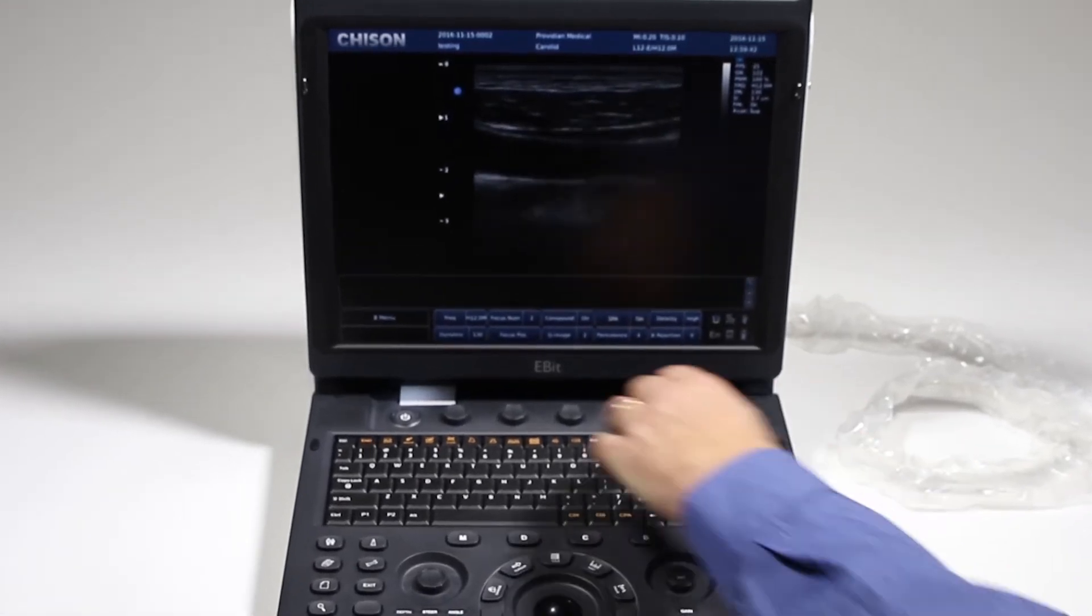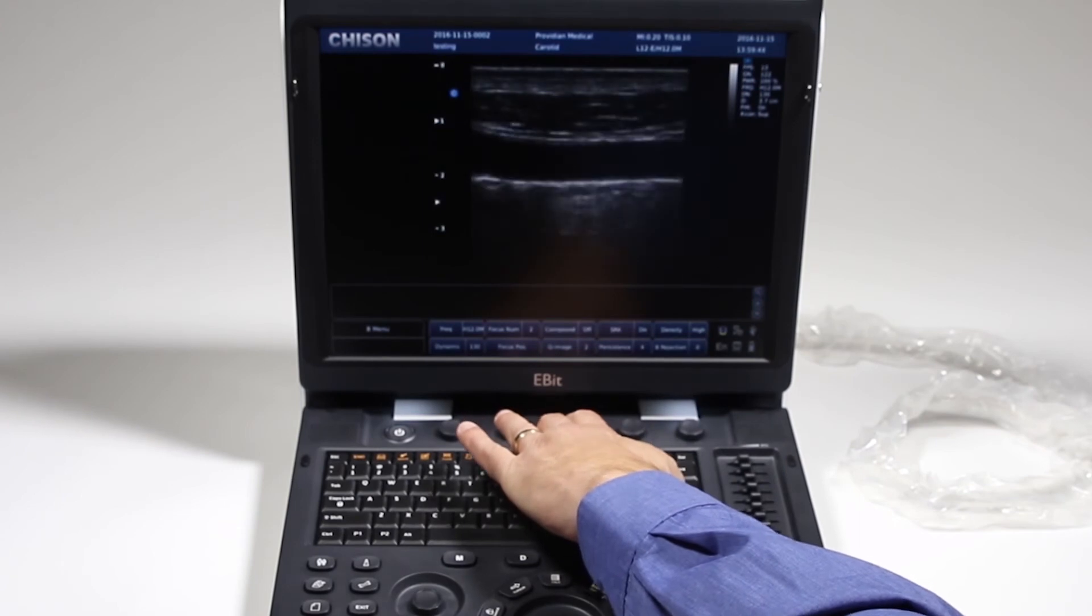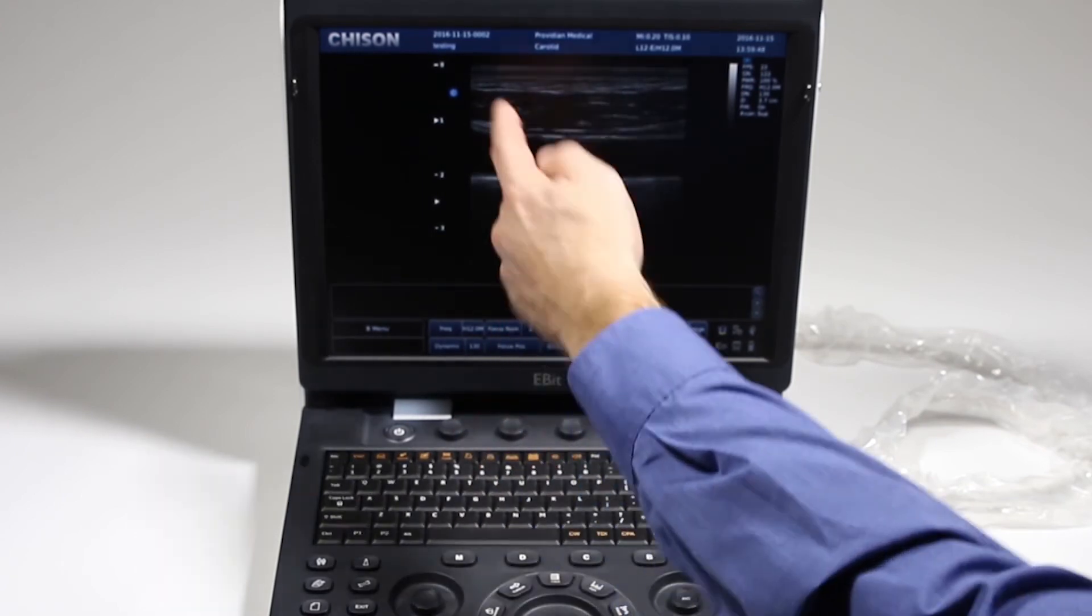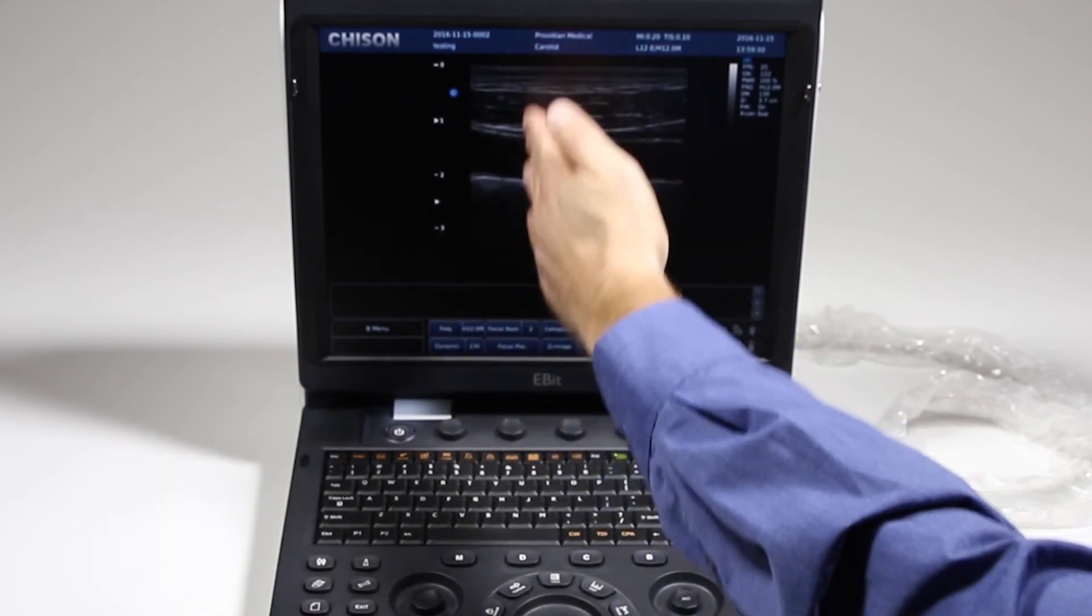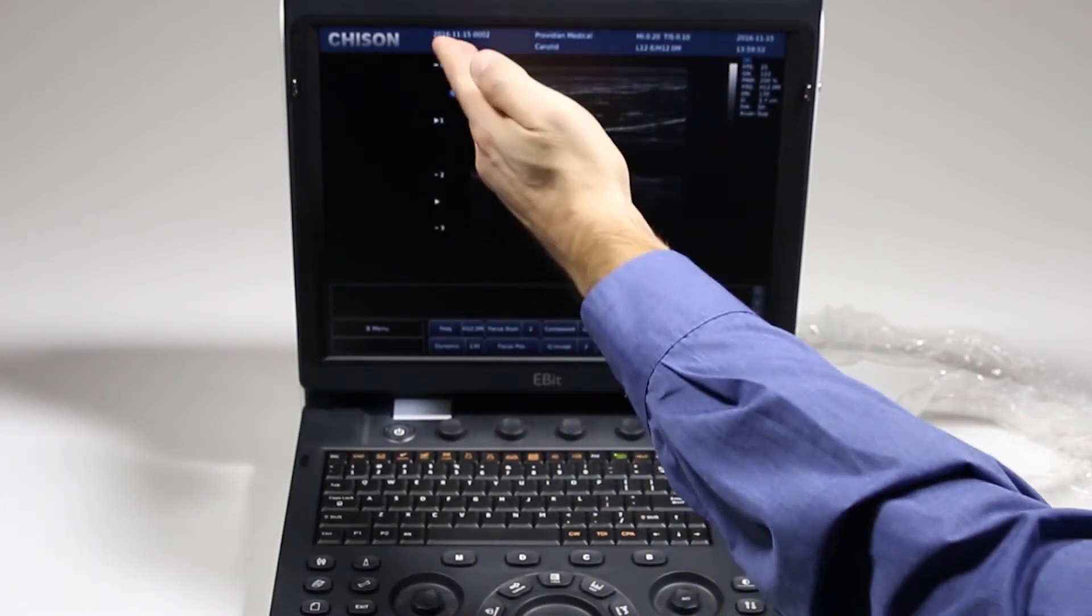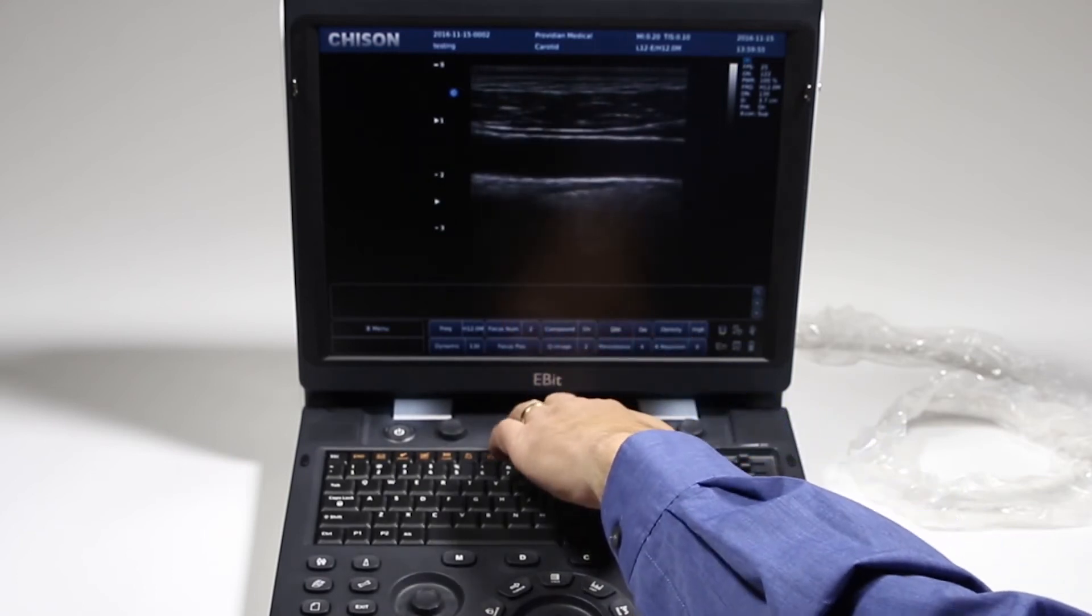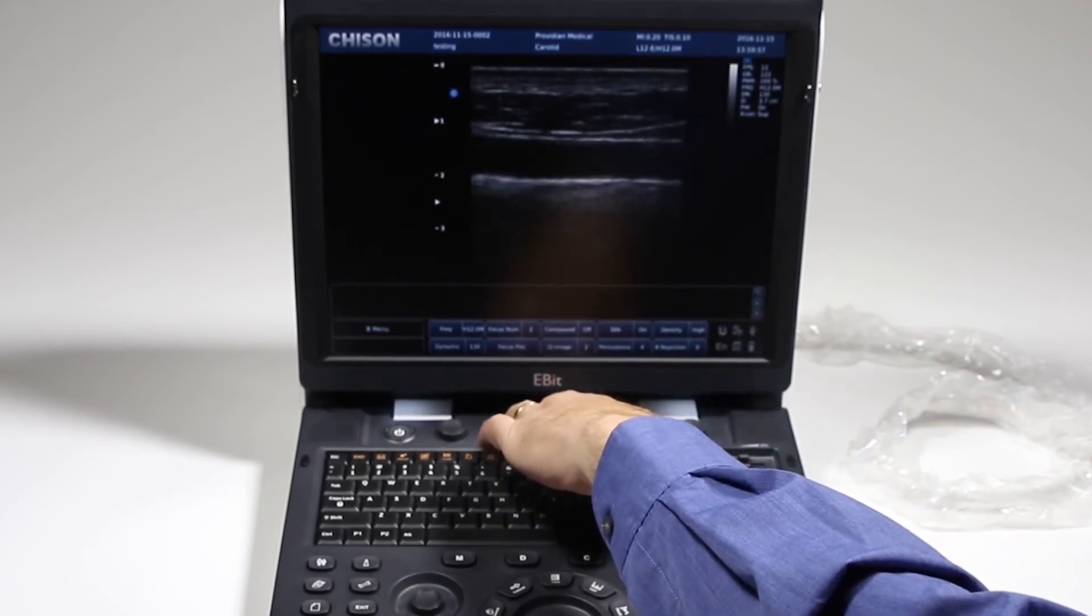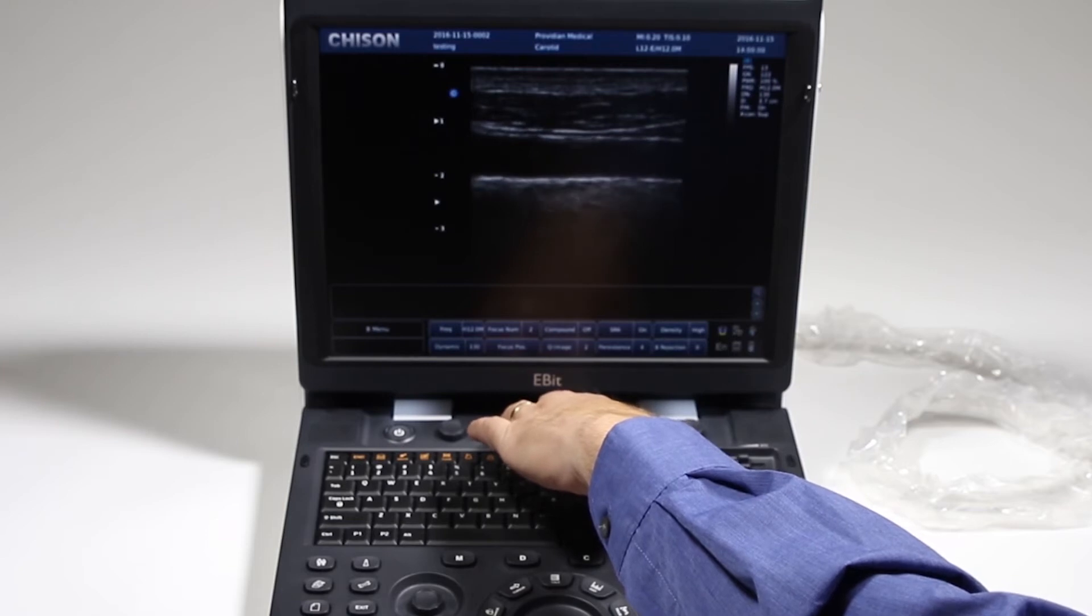We discussed compound imaging on and off, and you can see how that affects the image, going to something grainy or not. Compound uses multiple lines of sight instead of just perpendicular. It'll show lines of sight from this way and that to help clean up the image. You can see it has quite a difference on adding and removing artifact from the image.